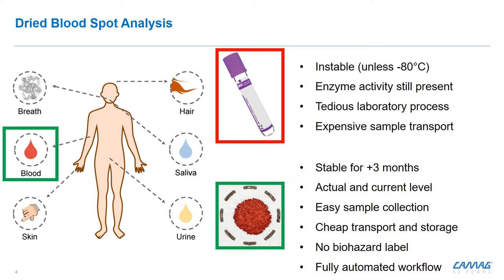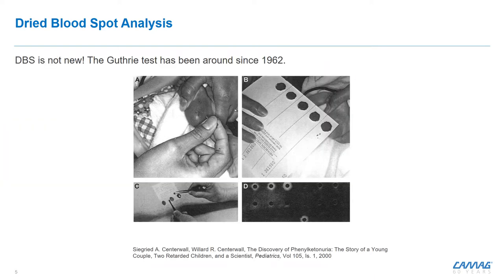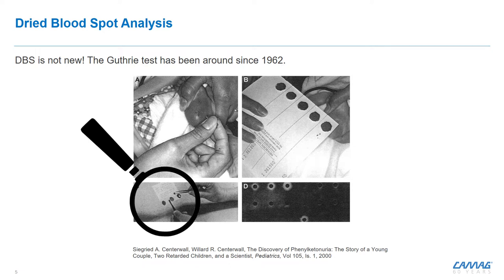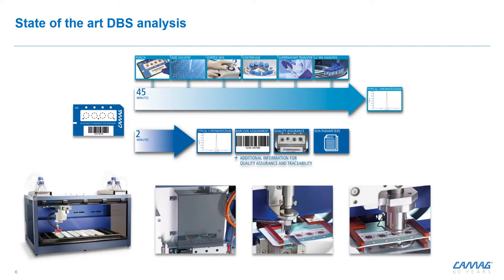Within the laboratory, we have fully automated processes to do the analysis. Dried blood spot analysis is nothing new — the first routine application goes back to 1962, where they punched out disks and then transferred them into a vial for extraction. We took this process and automated the whole workflow, so instead of punching these disks, we directly elute from the filter paper card into the LC-MS instrumentation or into a 96-well plate or vial.